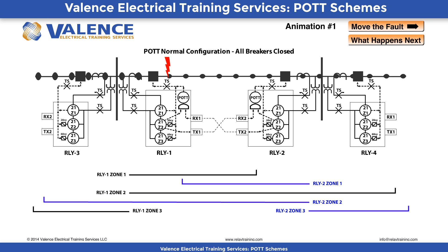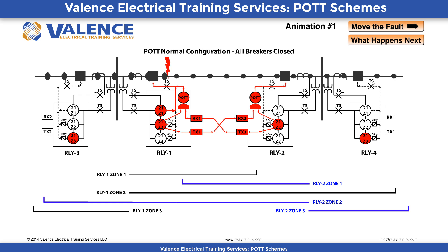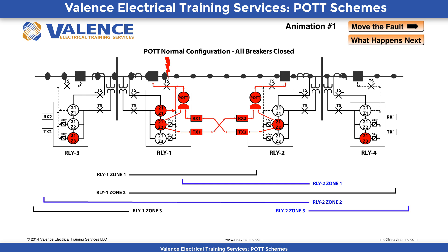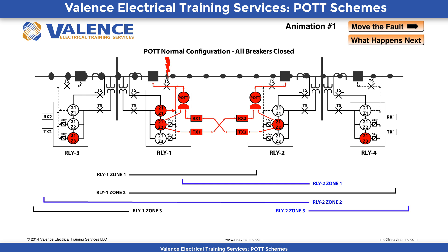Which elements will pick up in Relay 1 if a fault occurs close to Relay 1 as we show here? Which elements will pick up in Relay 2? Zone 1 and Zone 2 will pick up in Relay 1 because the fault is closest to Relay 1, while only Zone 2 will pick up in Relay 2. Relay 1 should trip instantaneously because of the Zone 1 pickup, but it will also send a POT signal to the other relay because it has detected a Zone 2 or potential overreaching fault on the line.